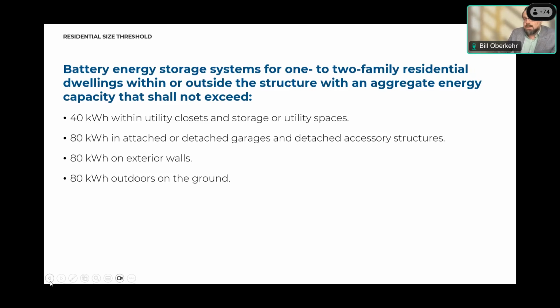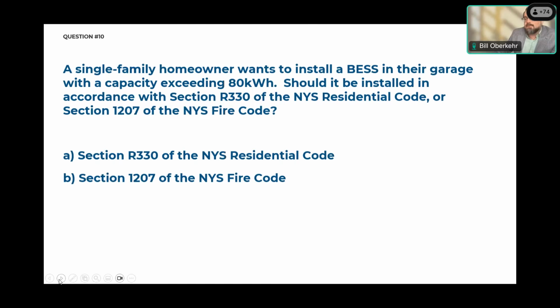We have another quiz question here. A single family homeowner wants to install an energy storage system in their garage with a capacity exceeding 80 kilowatt hours. Should it be installed in accordance with 330 of the residential code or 1207 of the fire code? This is probably the trickiest question. The answer is B. Since you're exceeding the 80 kilowatt hour capacity in the residential code, you are then looking to the fire code for how you deal with that installation, if you're going to be able to permit it at all.